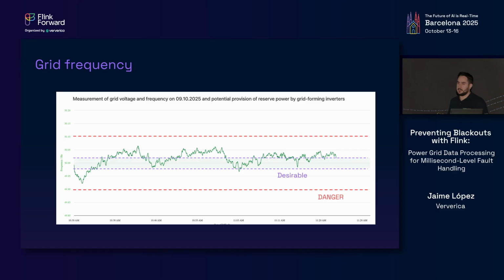And where this matters a lot is in frequency. This is a screenshot I took of the European TSO a few days ago, where they measured the frequency of the European grid at a couple of nodes. Frequency is the heartbeat of the grid. This is going to reflect the exact balance between generation and consumption. When you have more generation than consumption, frequency goes up. When you have more consumption than generation, frequency goes down.